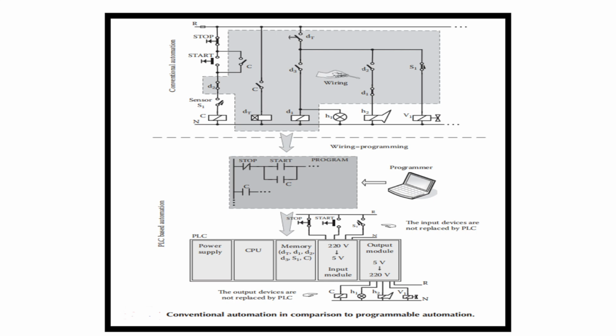The programming devices, used only during the programming stage, can be either dedicated digital devices or a personal computer equipped with specialized software. These programming devices mainly facilitate the conversion of a traditional hard wiring system into flexible software solutions and embed the necessary industrial automation components like auxiliary relays and timers within the PLC itself. As you can see in the diagram, the conventional automation in comparison to the programmable automation, you can clearly see the difference in the various parameters of the conventional automation as compared to the programmable automation. Consequently, the implementation of an industrial automation system does not require additional auxiliary devices and traditional automation circuit designs, which are often replaced by directly programming the PLC, or programmable logic controller.